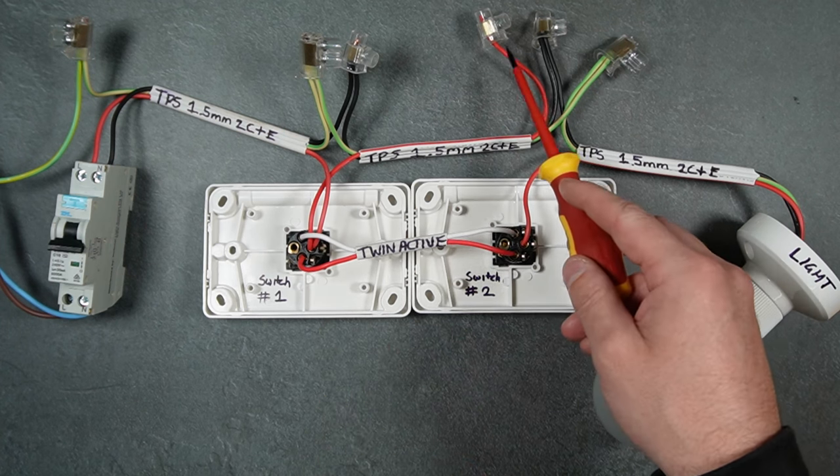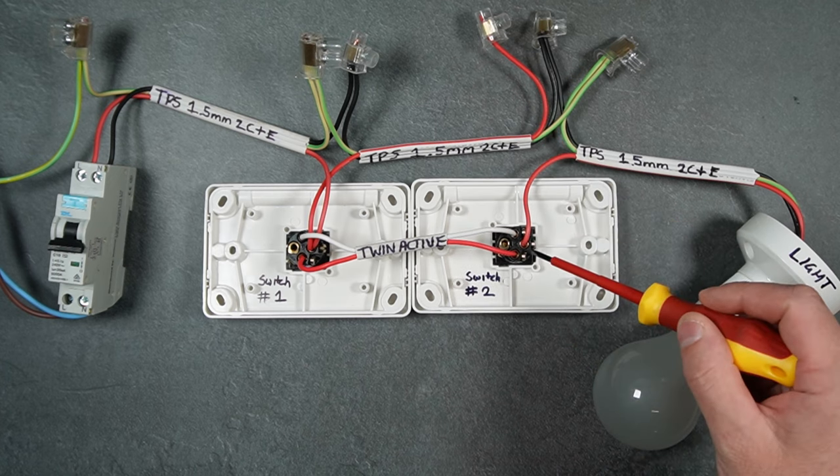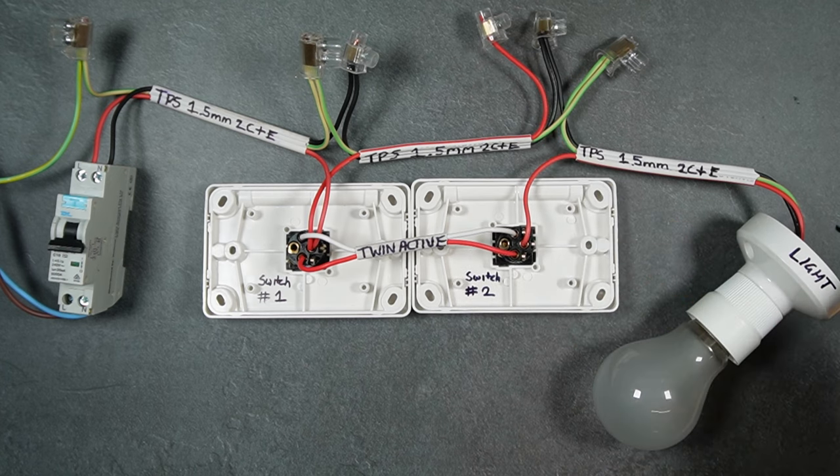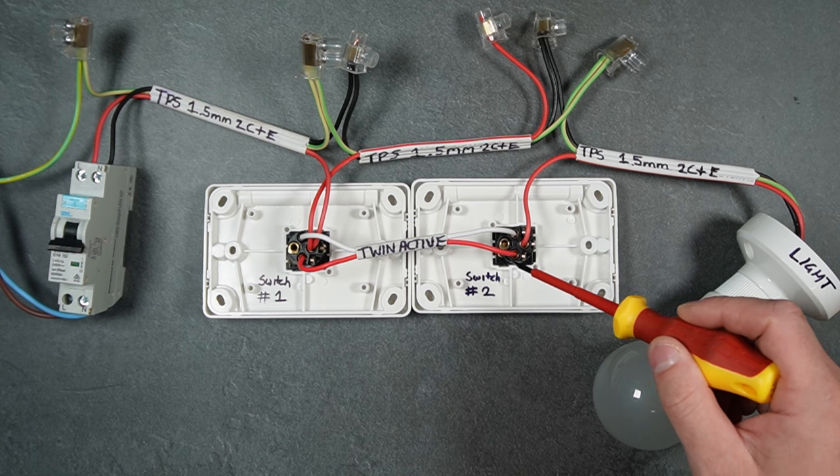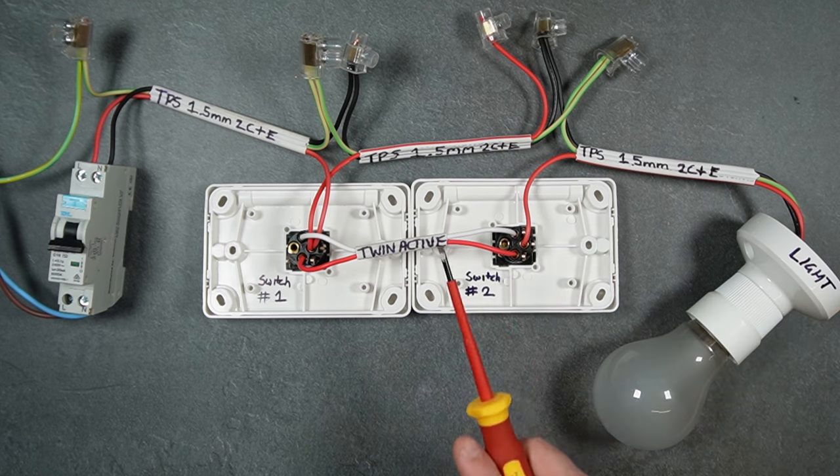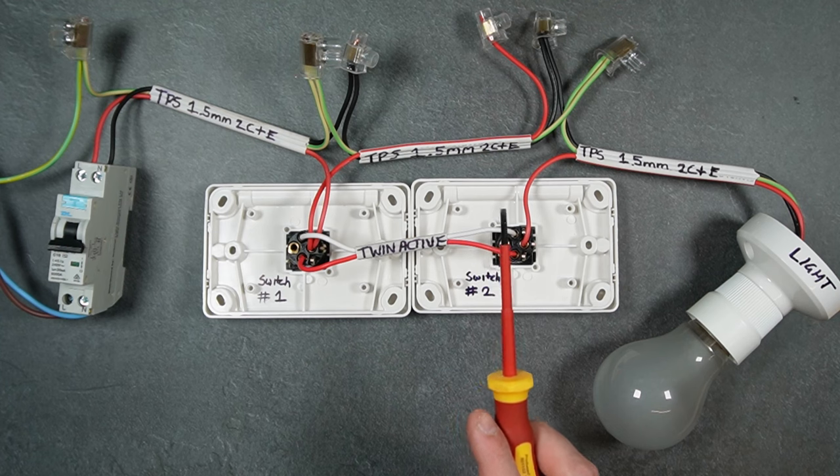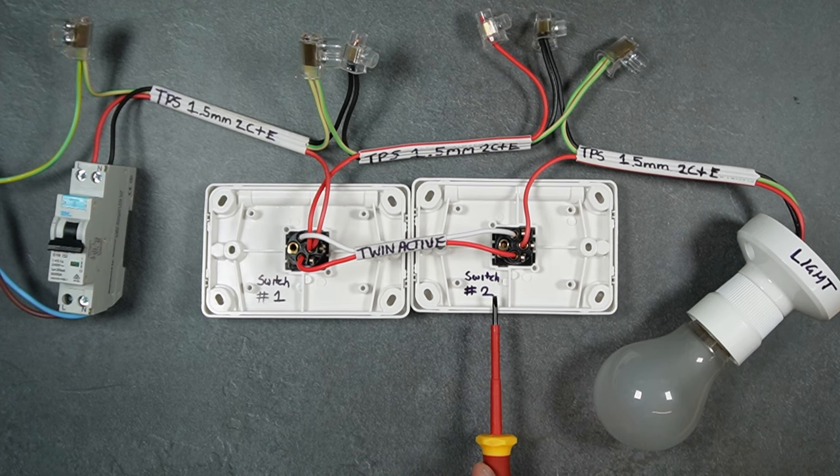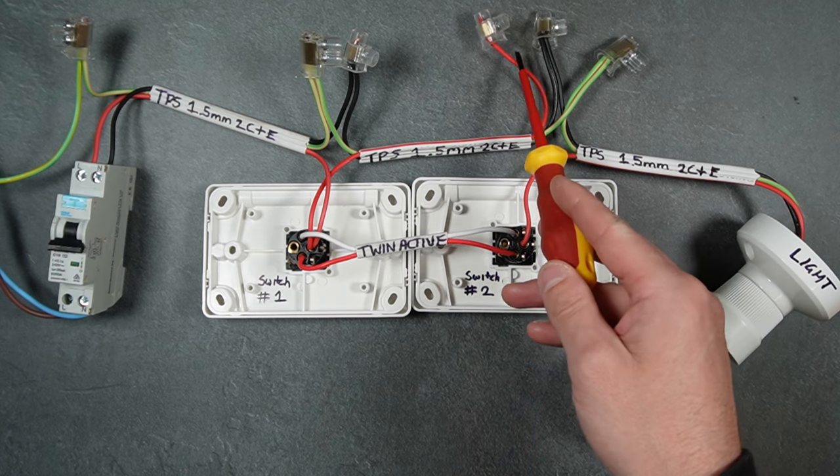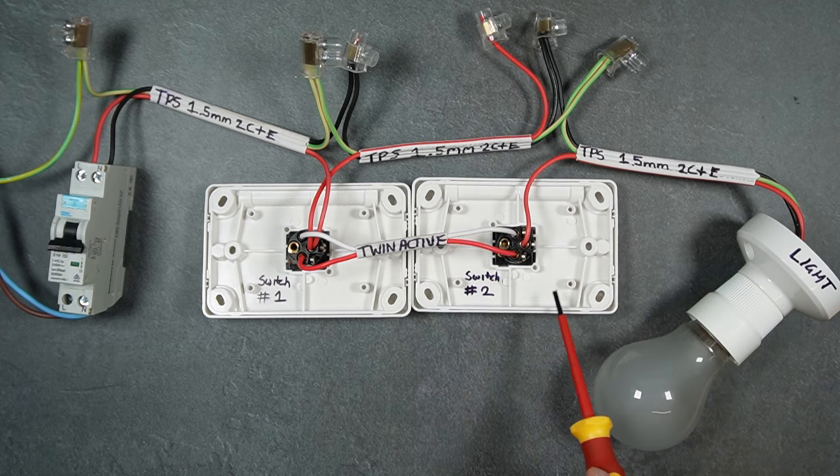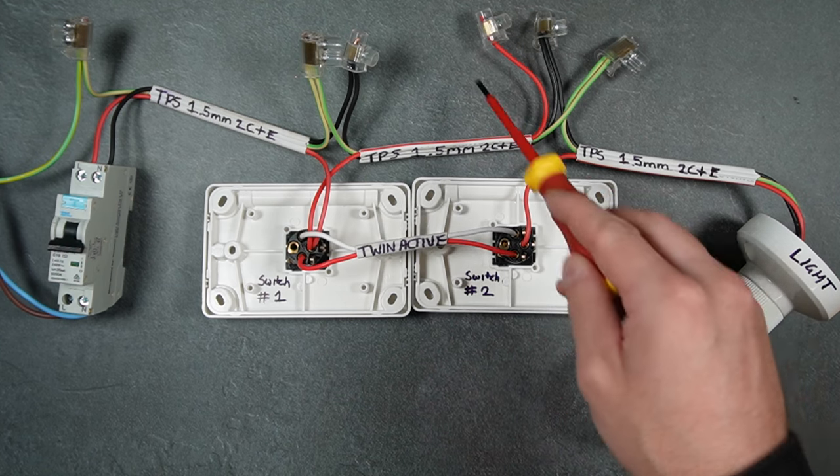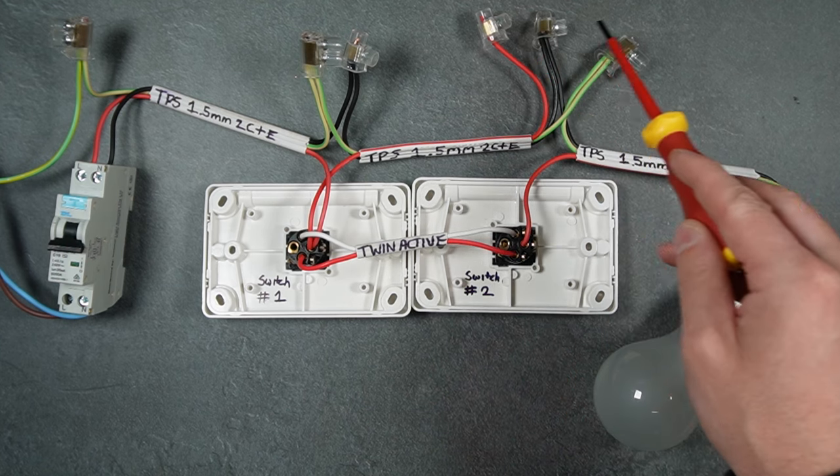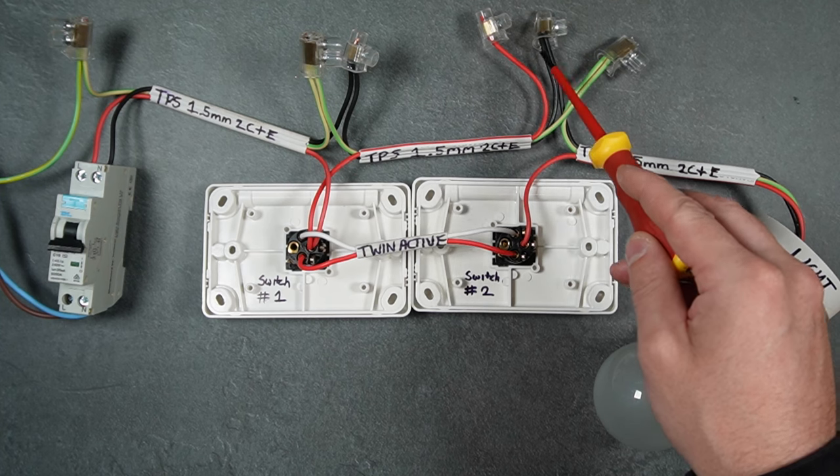Going back to this hard active - it does not go into the common because that's where the active from the white goes. If this is the end of the circuit, which means there are no other switches after switch number two, the hard active will go into a connector. But if there are other switches after switch number two, this active, neutral, and earth will join with another two-core and earth cable and go to the next part of the circuit to another switch.